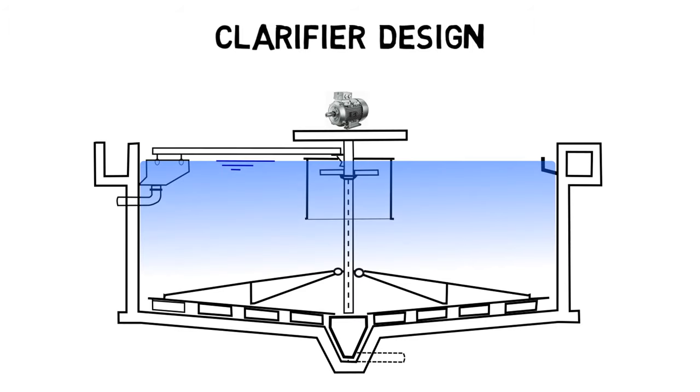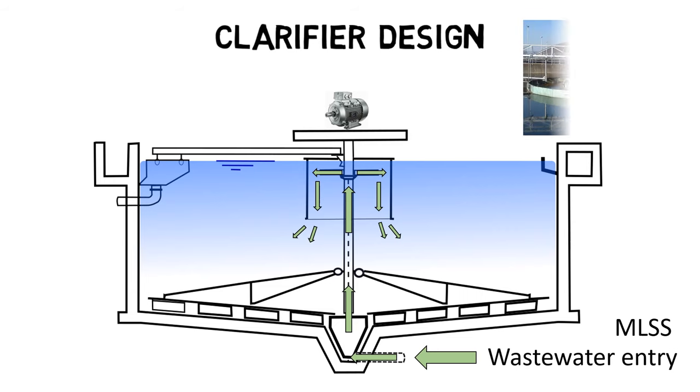Wastewater from aeration basins is usually entering the clarifier from a centrally located pipe. The entering wastewater is also known as the MLSS, mixed liquor suspended solids, which refers to the concentration of suspended solids from the activated sludge process.